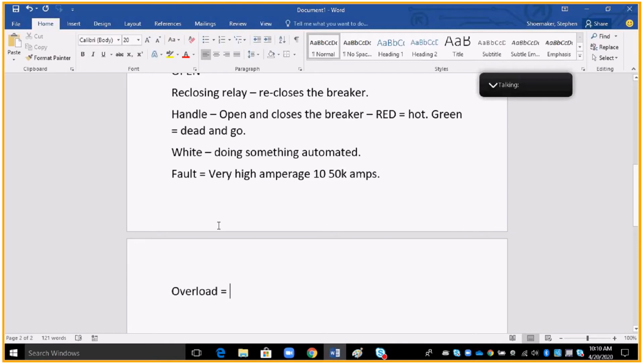Now, the situation is going to be the same almost. Instead of a very high amperage, 10 to 50,000 amps, my amps go over the relay, breaker, rating. So if I have a breaker that per phase does 600 amps, and that's what it's designed for, and for some reason on my circuit, say it's a real hot summer day or it's a real cold winter night, and that amperage starts raising and this goes to 650 amps, well, the relay's got to recognize that. I, one, don't want to damage my breaker, and two is my conductor and circuit out there, as far as this breaker and this circuit is concerned, I don't want to damage that either. So breaker will open.